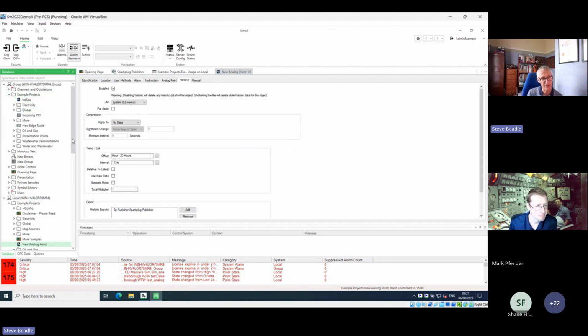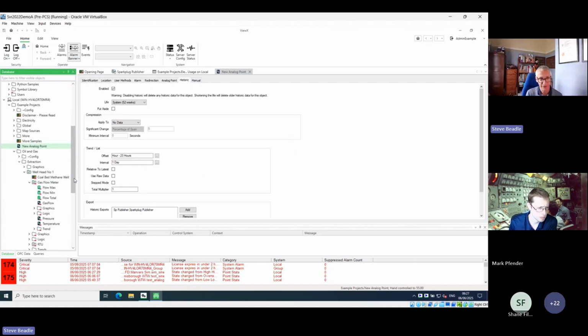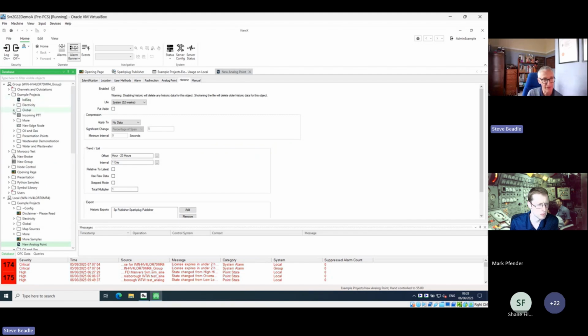And it will appear here not only with the values, but it will also have the configured properties such as the under range and over range and so on, if you've chosen to export those properties. So it could even include the alarm limits, the units names, the digital state names, and other properties of the point. And the target will therefore create all of this.